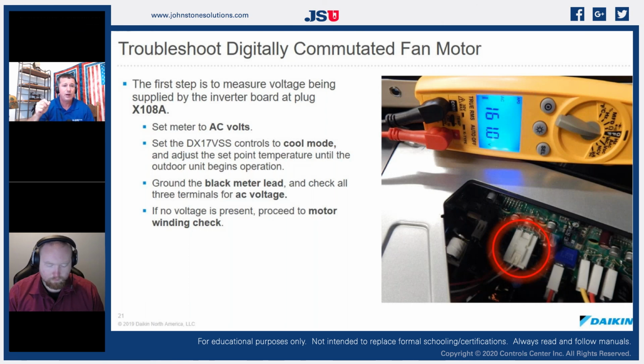So we went from a motor that had 2 windings, a start winding and a run winding, that had different resistances to them, so they had different diameters of wire, and we burn out the start windings pretty routinely in these things, right? Especially if we have a capacitor that fails on them. Well, with an ECM motor, we don't have that anymore. We have 3 windings that have all identical resistance and fairly thick wire. So we're not going to burn out windings like we used to. So it's super easy to check these things.